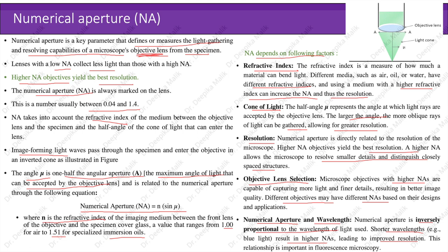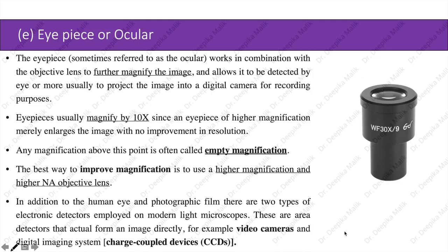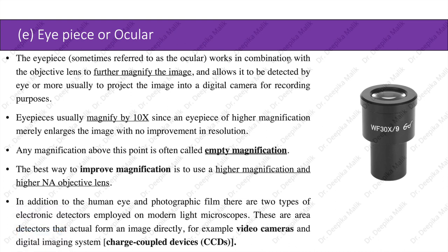The eyepiece or ocular lens works in combination with the objective lens to further magnify the image and allows it to be detected by eye or projected into a digital camera for recording. Eyepieces usually magnify by 10x; a higher magnification eyepiece merely enlarges the image with no improvement in resolution — any magnification above this point is called empty magnification.